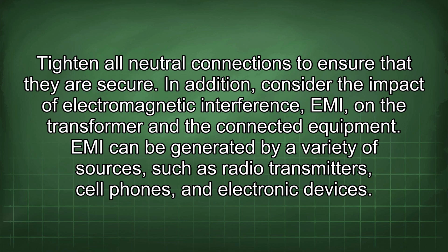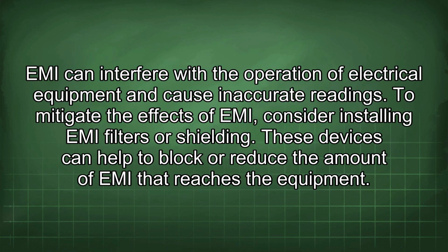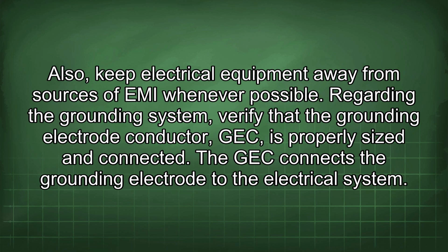In addition, consider the impact of electromagnetic interference (EMI) on the transformer and the connected equipment. EMI can be generated by a variety of sources, such as radio transmitters, cell phones, and electronic devices. EMI can interfere with the operation of electrical equipment and cause inaccurate readings. To mitigate the effects of EMI, consider installing EMI filters or shielding. These devices can help to block or reduce the amount of EMI that reaches the equipment. Also, keep electrical equipment away from sources of EMI whenever possible.